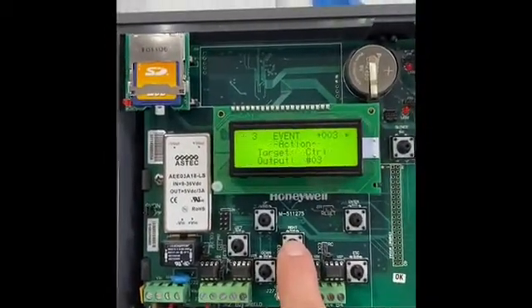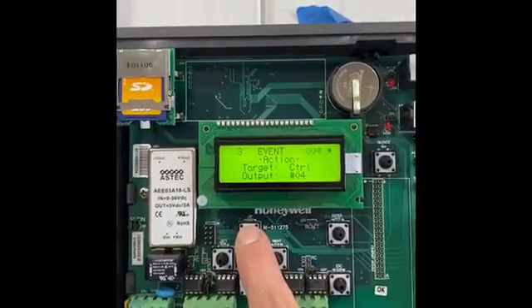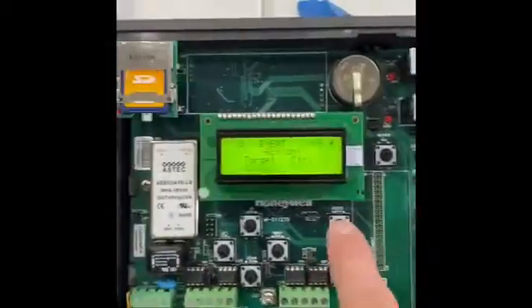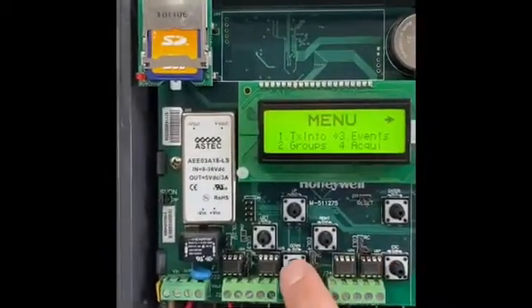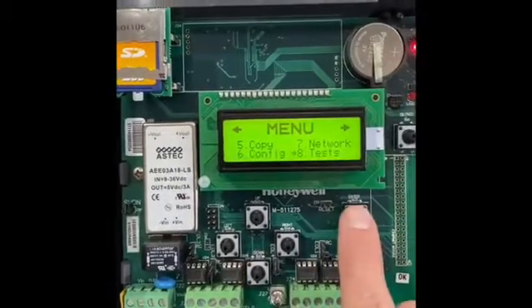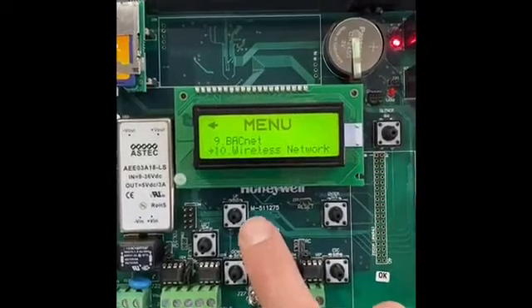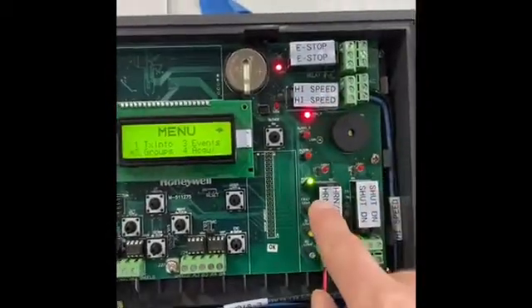You can create new events by selecting here — you go up; I made a four just for testing, and when you get to five the output shows a question mark. So you can set another sequence to control one of the outputs you're already controlling. There's also an internal buzzer you can use. The other big thing is the test mode — it will enable all the alarms and engage all four of these relays so you can test whatever you have as output. I'm not going to do it so I don't accidentally set something off for the guys in there.